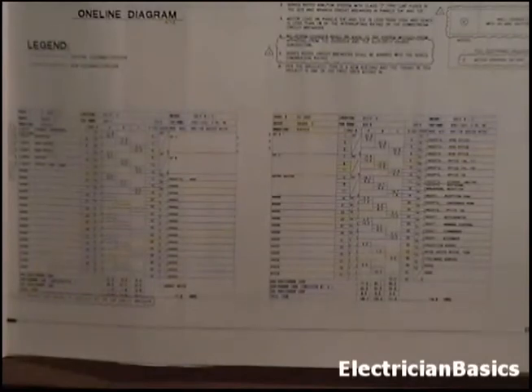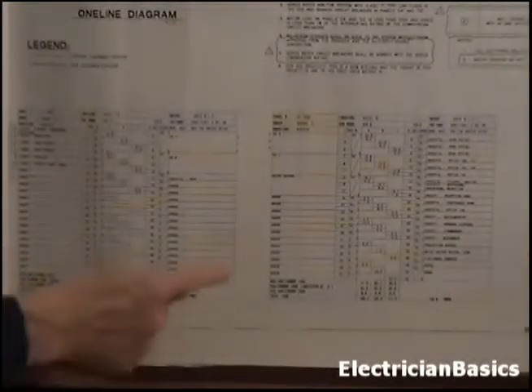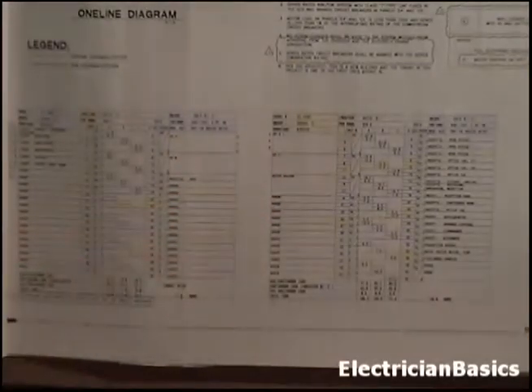And when you do startup, you're going to go through and turn on each circuit, and then you're going to be testing your outlets or making sure that all your lights come on or making sure that all of your equipment operates. So you're going to be doing that on the job anyway for real. So isn't it a good idea, I think it is, that before you build it, you become very thoroughly familiar with the locations of every circuit. So that's what I want you to do. So go through the plans right now. It's going to take you a little bit of time, but make sure, and you got a lot of clues here. Okay, this tells you it's lighting in the storage and break room or in offices, okay, or the conference room. This tells you heat pump A, heat pump C, the water heater, okay?